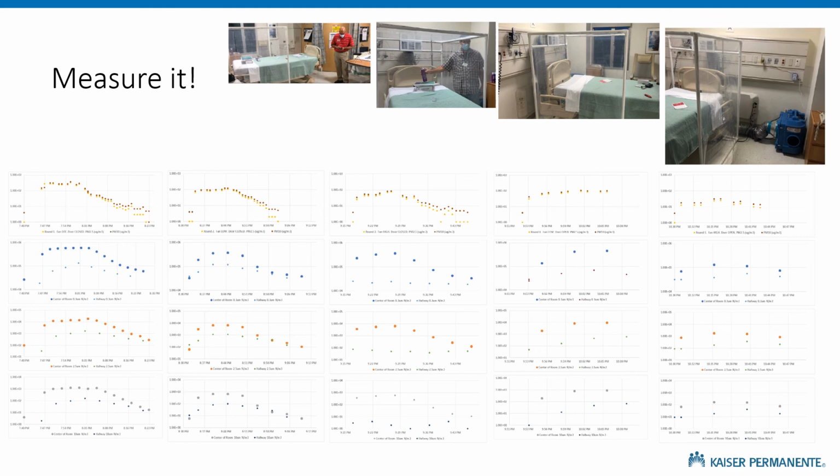I should say that I consider this to be a failed headboard test. If you remember the calculations I did 6 slides ago, we want those headboards to capture 90% of the particles generated underneath them. Hey, even 50% would be something very worth talking about. This data doesn't show that at all. And in review, the test is totally wrong.